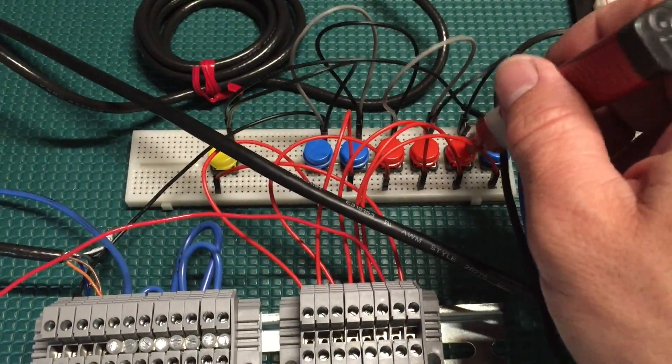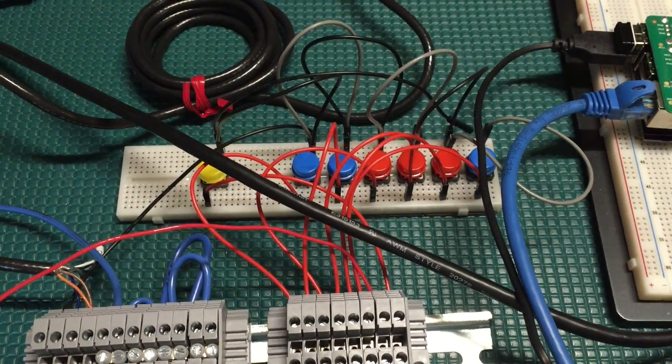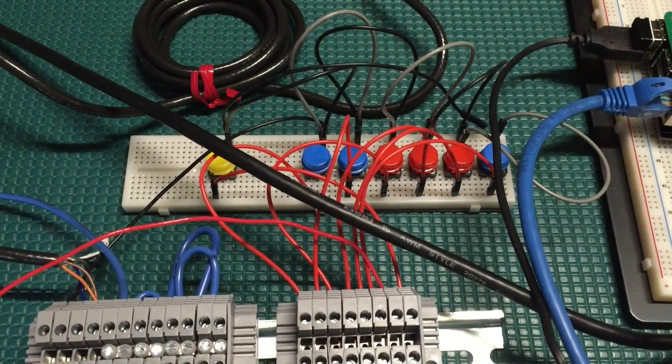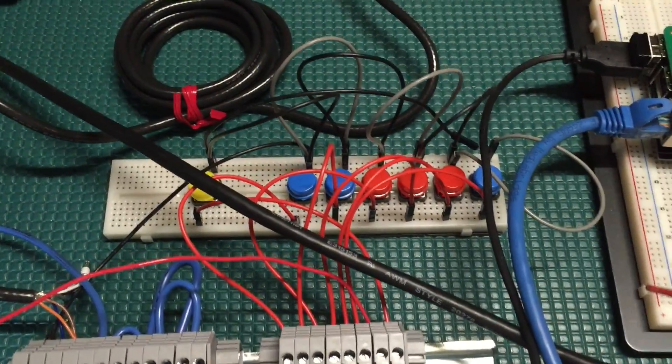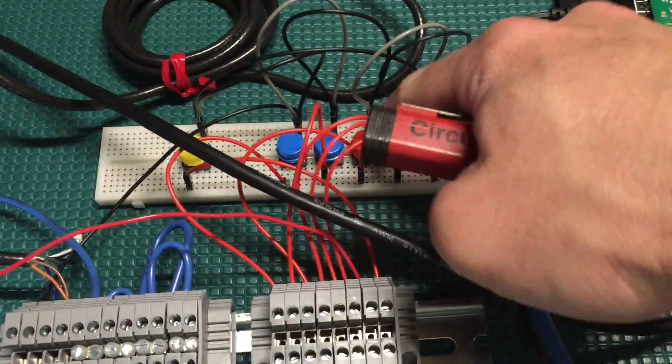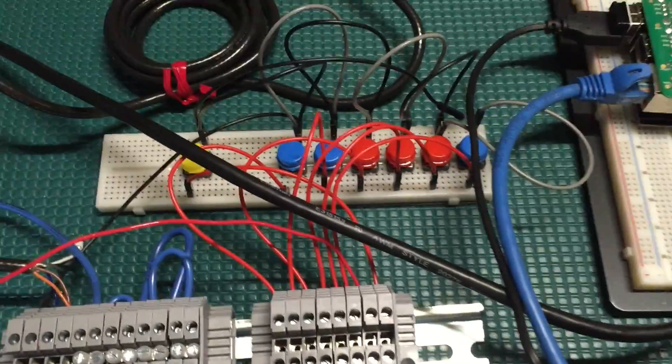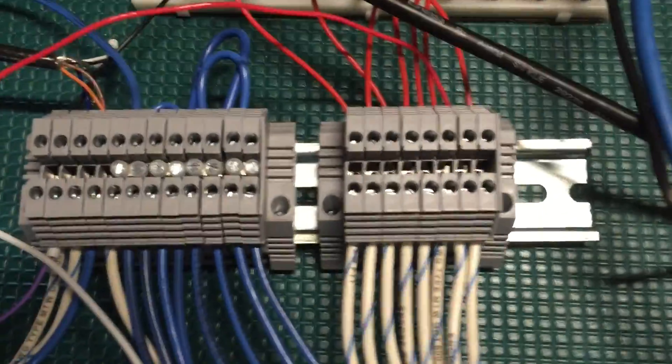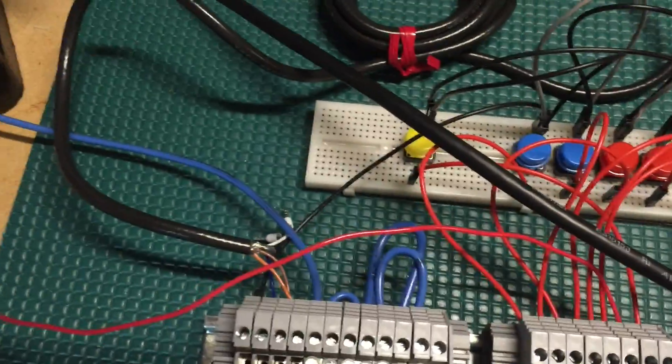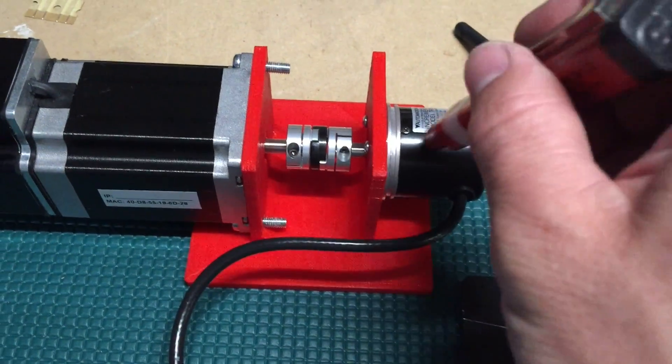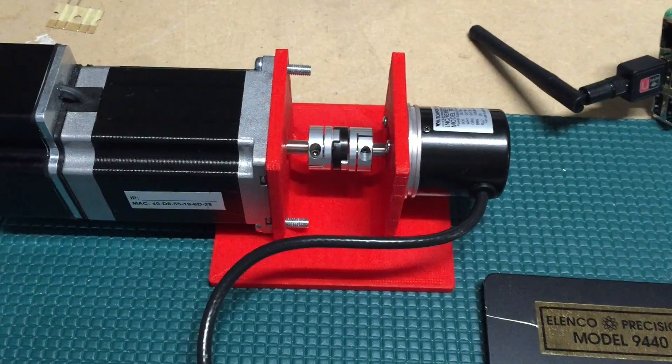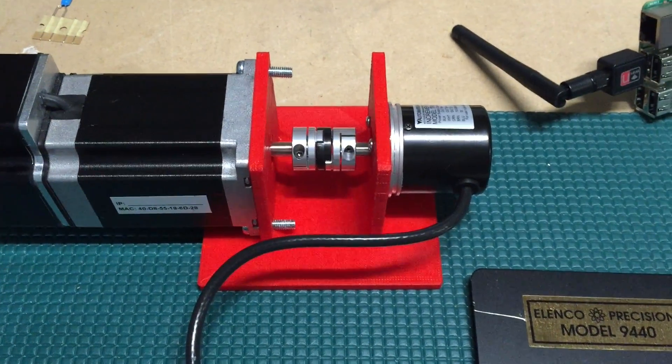These switches here, or these buttons, these are switching 24 volts, and that is to emulate the contact closure on the detector side of things. So when it detects a holiday, I can emulate that by pressing these buttons. And then it will display it on the screen. The rest of this, I'm looking at the Z-pulse coming from an encoder, AutomationDirect, this guy. It's just a 1024-pulse-per-rev encoder.